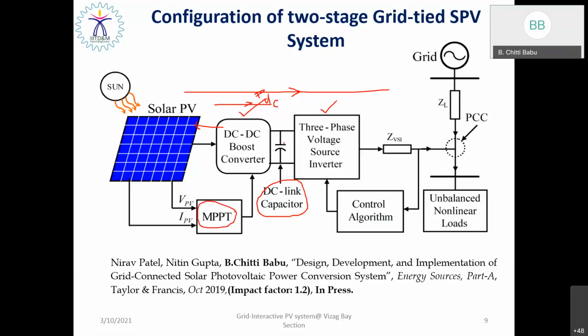And then the power available at the DC link capacitor is DC. Again, that will be inverted into AC, which is controllable. Then the controllable AC will be injected into the utility grid. Then virtually we have a point at which we connect a nonlinear unbalanced electronic load, called the point of common coupling. So the point at which nonlinear loads are connected to the utility grid is what is called the PCC.